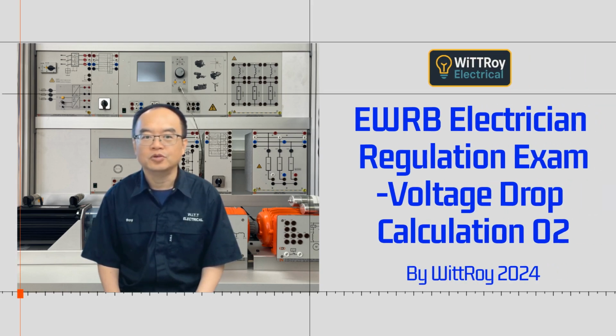In my last voltage drop video, I mentioned that AS/NZS 3000:2007 contains a simplified method for calculating cable voltage drop, found in Appendix C, paragraph C4 on page 376. Today we'll be guiding you through this method.